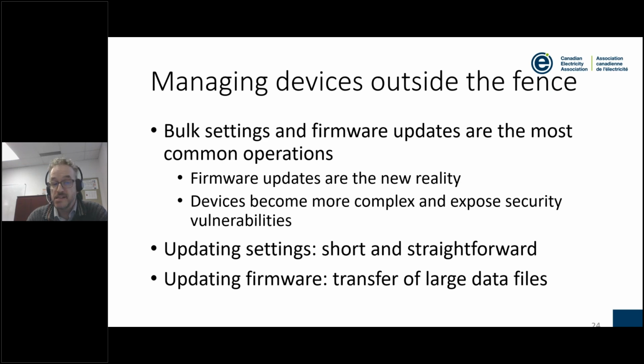Updating settings, essentially sending a settings update to a number of devices, is typically pretty short and straightforward, still manageable manually, taking just a couple of minutes per device. Now, updating firmware typically requires a transfer of a much larger data file. If done on only one or a handful of devices, it wouldn't be much of an issue. But typical distribution utilities might be managing hundreds, if not thousands, of devices, so every minute counts in that case.